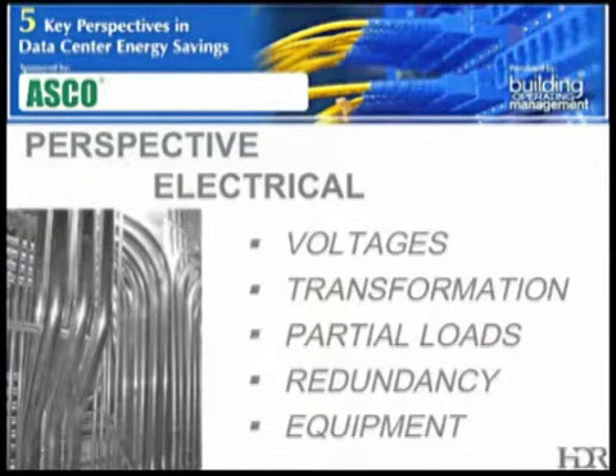and what that time outage is and how that affects your equipment downstream. So that could range anywhere from 30 to a quarter cycle, depending on the technology used there. Robert mentioned on-site power generation and the efficiencies of that. If you look at using some of the alternate technologies that are out there, whether it's wind, PV, or fuel cells as an on-site generation, you may get more efficient use of clean or free fuel sources, and that can increase your efficiency. Also, while the cost per kWh may be higher than standard diesel generators for these alternative energy sources, having the on-site generation there will increase your reliability by giving you independence from a utility grid, and that may outweigh these costs.